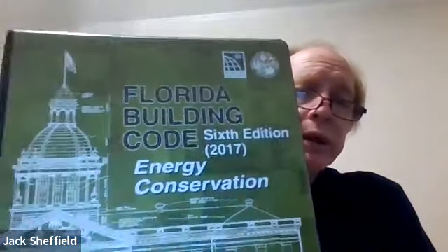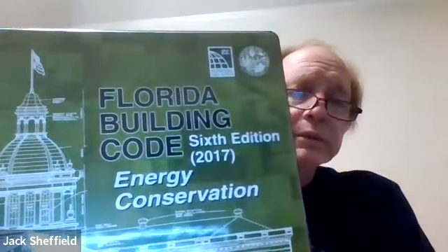General good information is in the Energy Efficient Building Construction in Florida. The Florida Building Code Energy Conservation is a book of rules, okay? Minimums and maximums. It's got to be a certain way, all right? The maximum air infiltration for a window is 0.3 cubic feet per minute. It talks about skylights and the most you can have in skylights. It talks about your different building components and the U factors that they have to be by code and so forth. So if it's an energy conservation question and it's one of those what we call shall-be questions, it's got to be a certain way, then there's a good chance that it's Florida Building Code Energy Conservation.